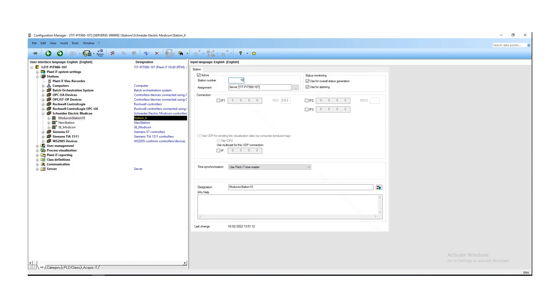You have to set the station number — this is the unique number of the Modicon PLC in the plant IT system. The next important step for connecting the PLC to the plant IT system is to set the correct IP address, for example 192.168.7.110. Additionally, you can activate multicast for UDP connections for sending visualization data from the PLC to the server, and set up time synchronization — here it is set to use the plant IT master.